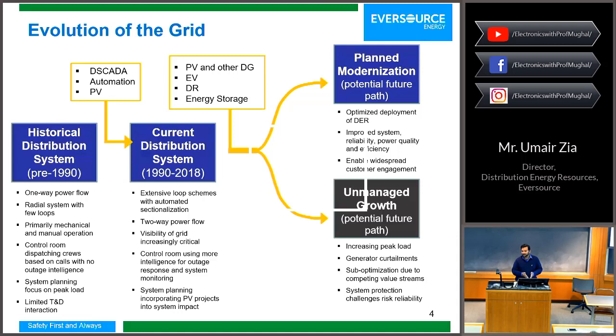With telecom automation, we installed switches that all integrate with each other, building a sequence that automatically detects where the fault happened and reconfigures itself in literally seconds. We used to take hours to restore service; now we can isolate the fault to exactly where it is, or to as minimal a region as possible, and restore everybody else through different circuit ties. So that was one step forward from the old historic grid.